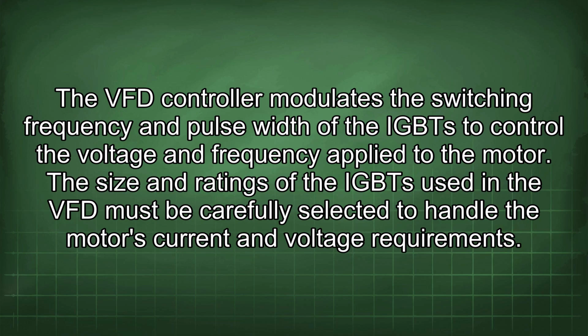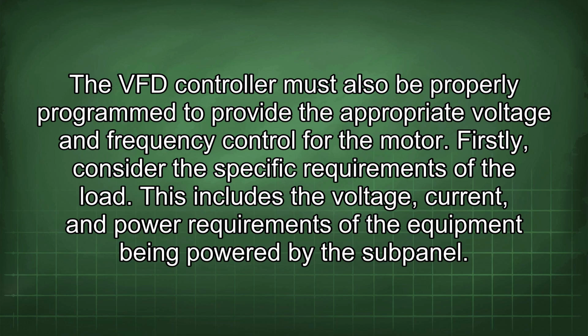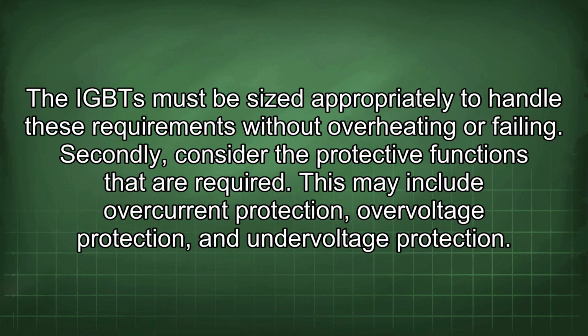to the motor. The size and ratings of the IGBTs used in a VFD must be carefully selected to handle the motor's current and voltage requirements. The VFD controller must also be properly programmed to provide the appropriate voltage and frequency control for the motor. Firstly, consider the specific requirements of the load. This includes the voltage, current, and power requirements of the equipment being powered by the subpanel. The IGBTs must be sized appropriately to handle these requirements without overheating or failing.